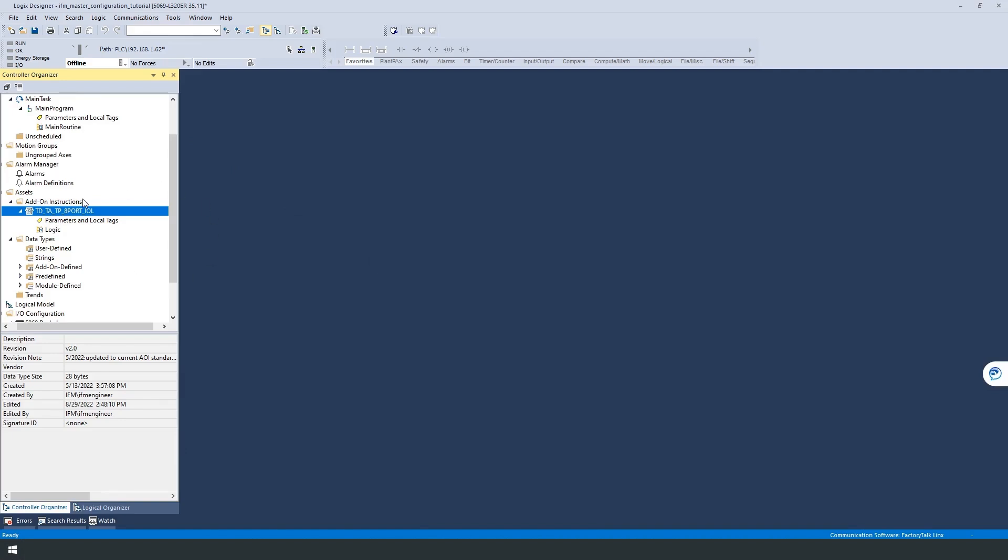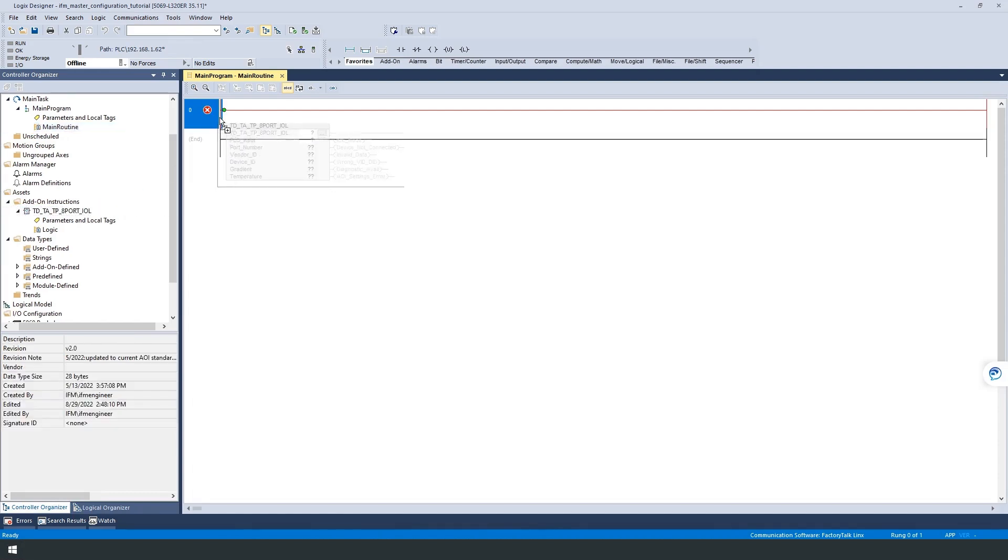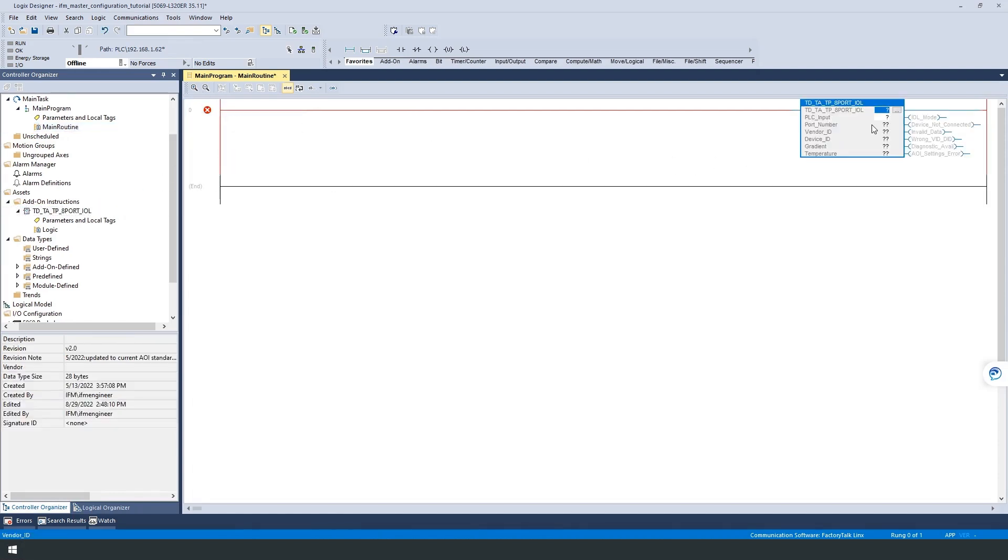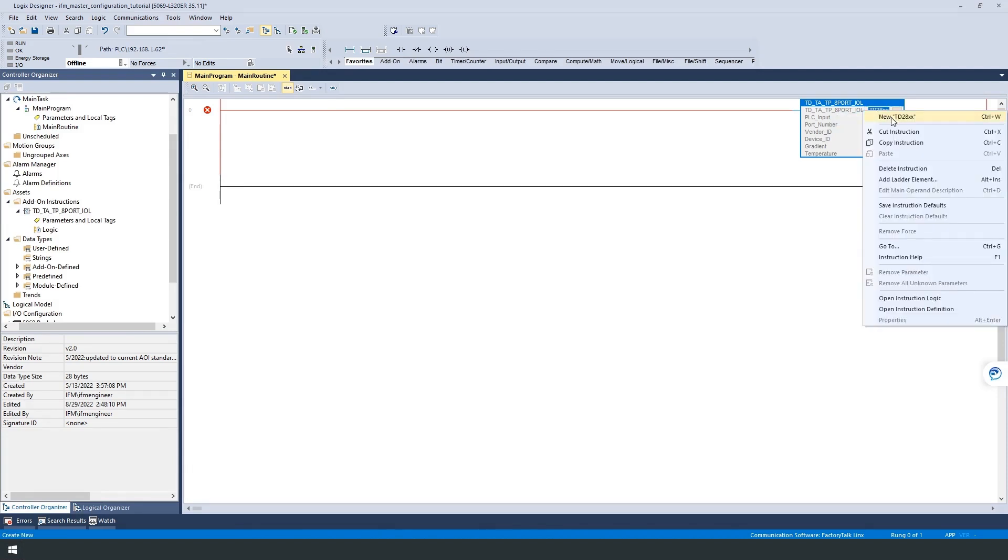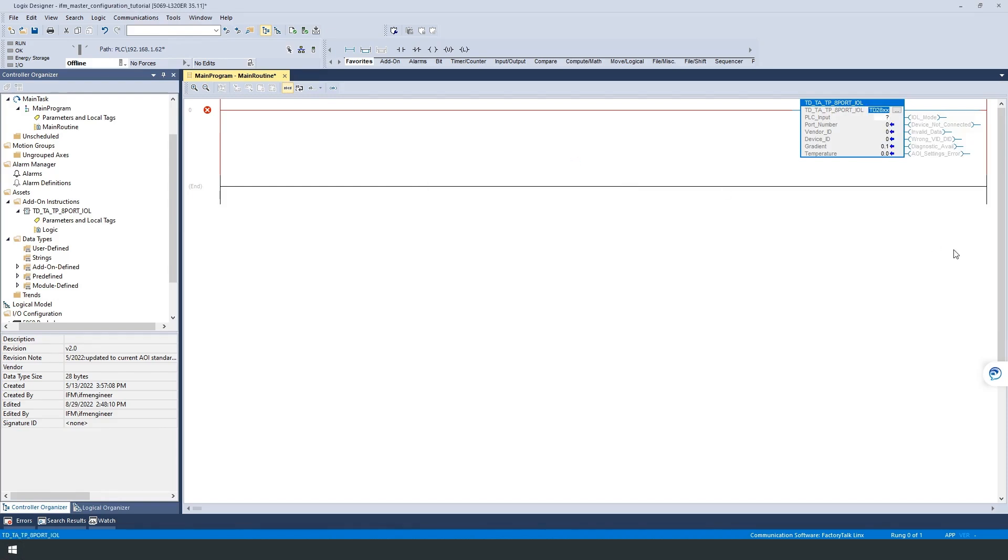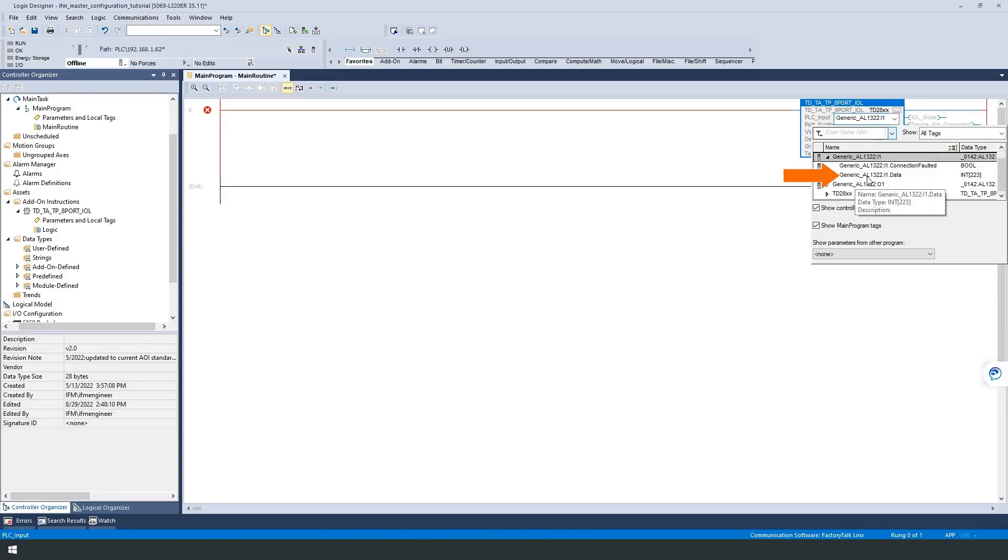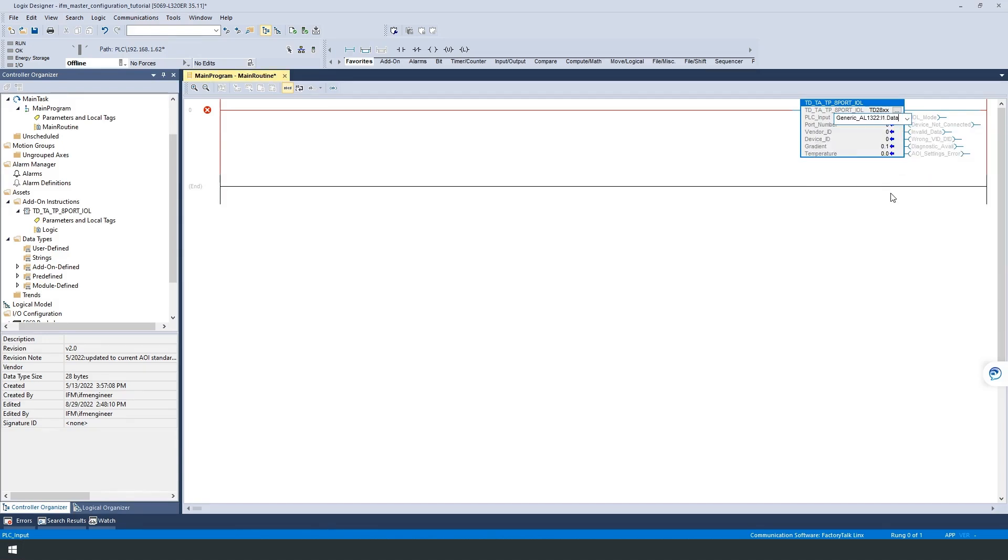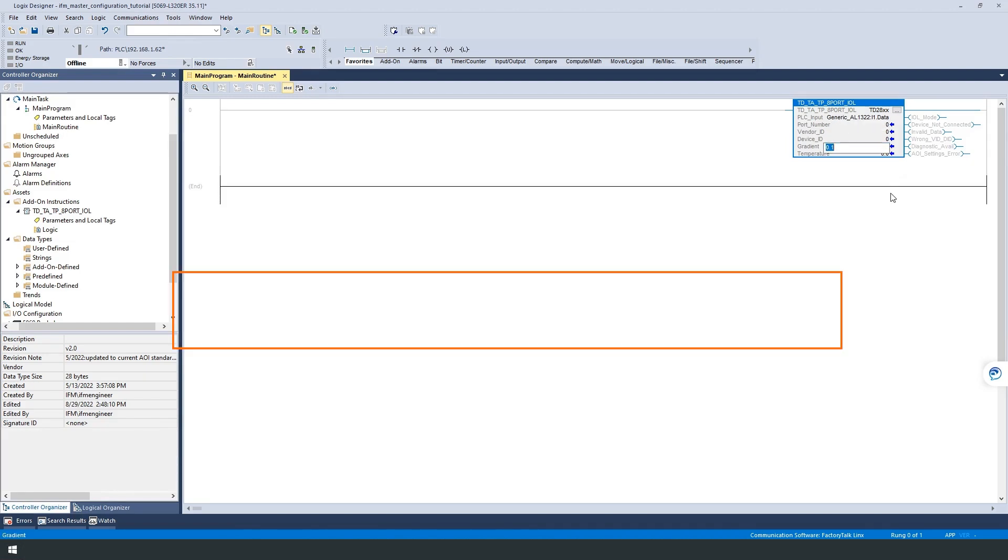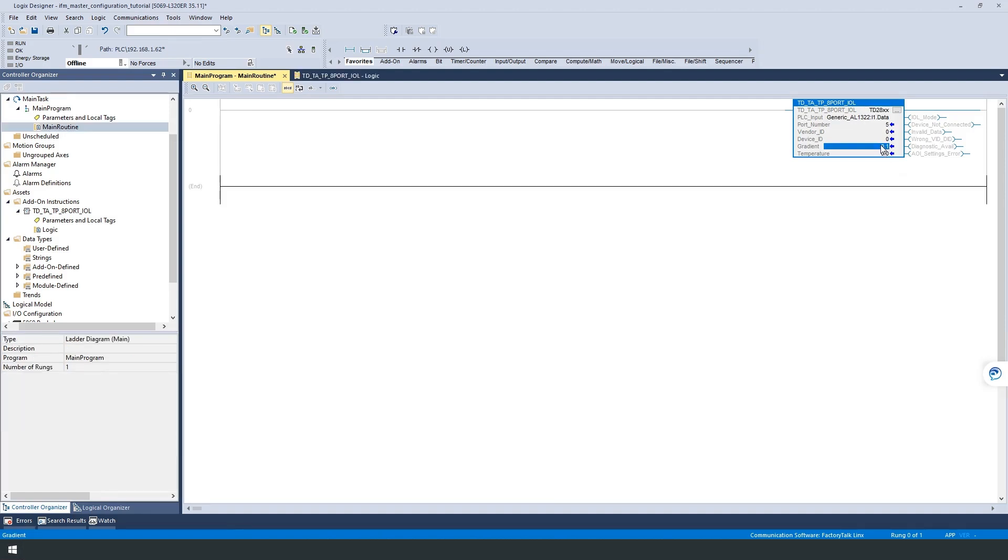After the import is complete, we go to our main routine and add the instruction via drag and drop. To parameterize the block, we start by giving the instruction a unique name. Select our IO-Link master's input array. Choose your IO-Link master colon i1.data to read the data from the sensor at port number 5. Vendor and device ID belong to the output data of the sensor, just like the temperature value. The only difference here is that vendor and device ID are fixed values that are assigned by the manufacturer. The temperature value, of course, is a variable process value. Last but not least, we need to check if the preset gradient for calculating the temperature value is correct.